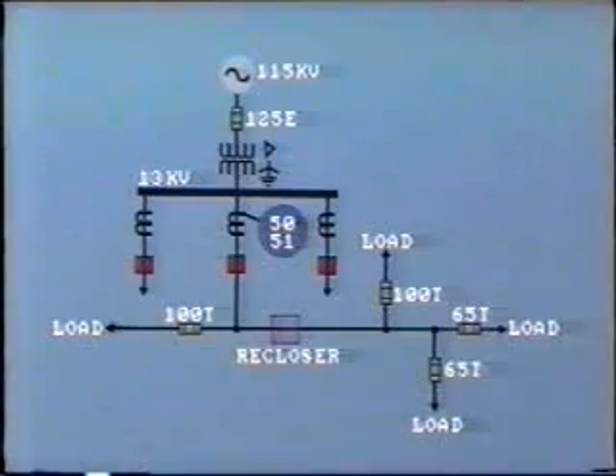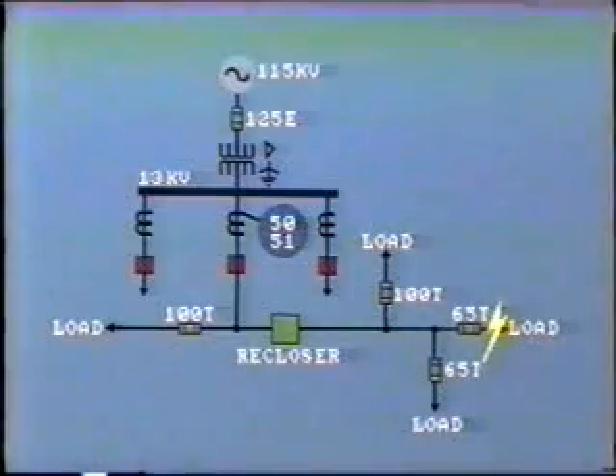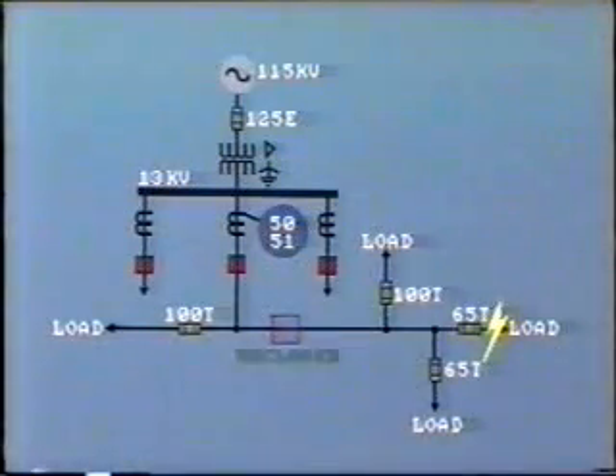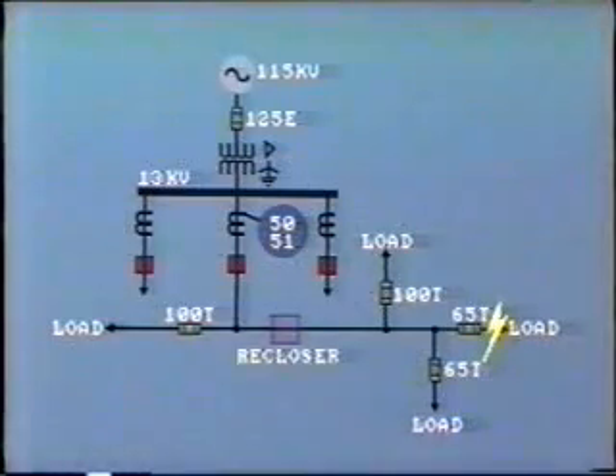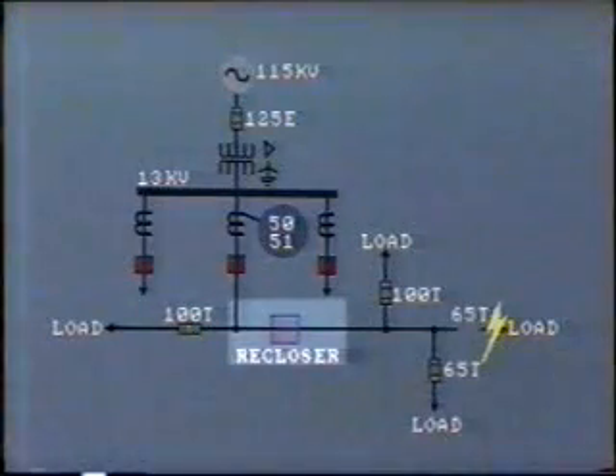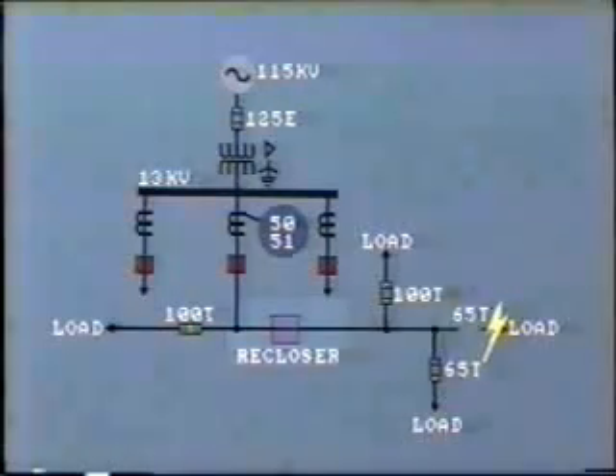For example, a temporary fault out here would cause the recloser to open on its instantaneous setting. It will then reclose after a short time interval, say 3 seconds. However, if the fault were permanent, the recloser would open again, but only after a time interval. However, before that time, the local fuse will operate to isolate the faulty circuit, so the recloser remains closed.